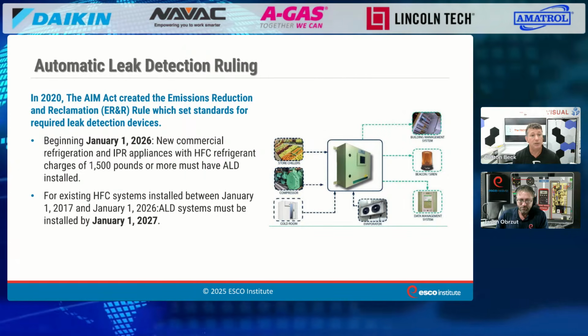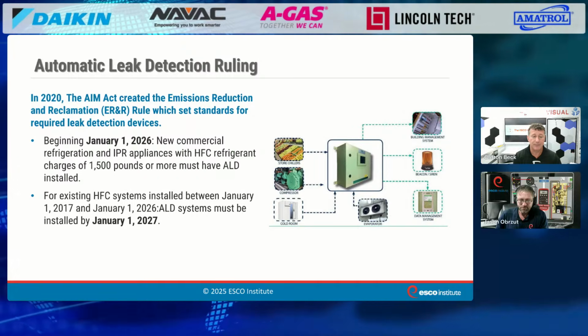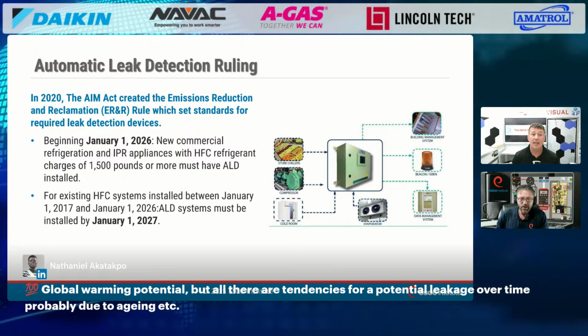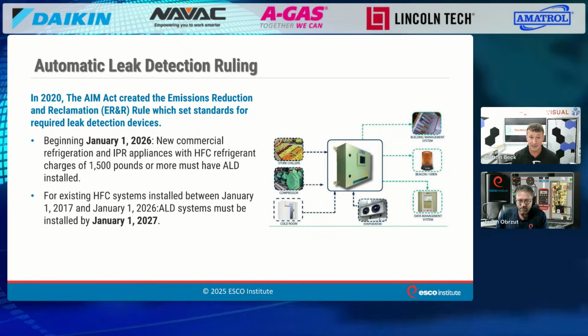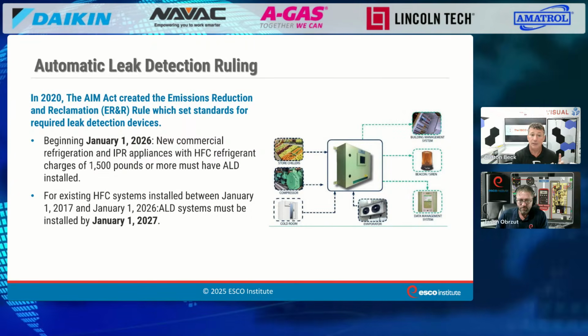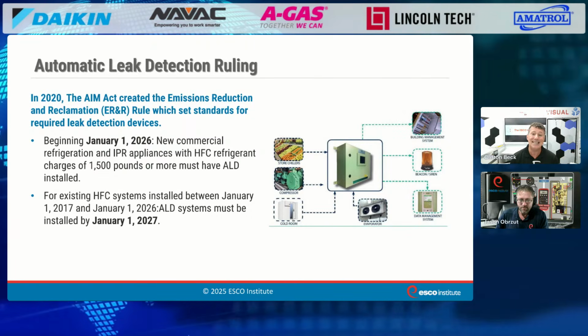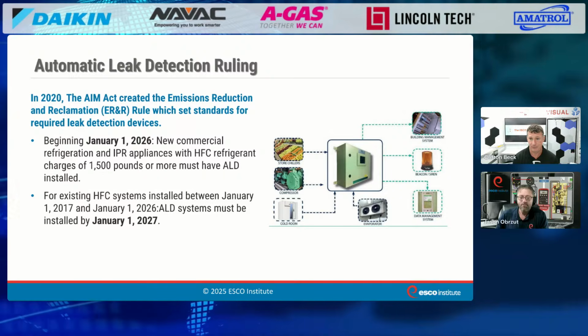So it falls into basically two categories. If we're doing a new installation of HFCs with 1,500 pounds, it's required, period, not even an option, on the installation, within 30 days of the installation. If it's an existing system that was built after January of 2017, it has to be retrofitted with one.